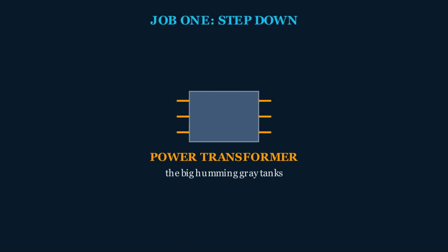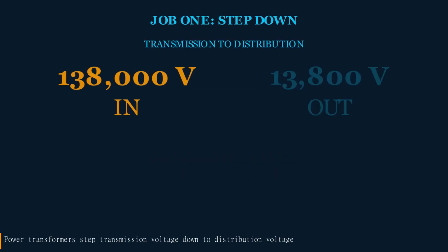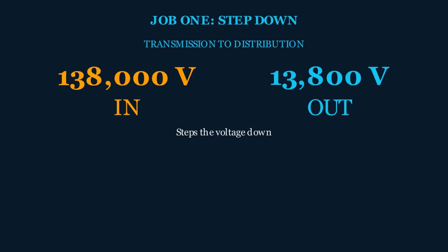And it's the first thing you can actually pick out through the fence. The biggest objects in the yard, those giant gray tanks, often with rows of radiator fins on the sides and a steady low hum coming off them, are power transformers. This is where the hum comes from. A transformer's whole job is voltage. It takes the high transmission voltage in on one side and hands out a lower voltage on the other. A line might arrive at the substation at 138,000 volts, and the transformer steps it down to something like 13,800 distribution voltage, the level that goes out on the poles or the underground cables running down your street.